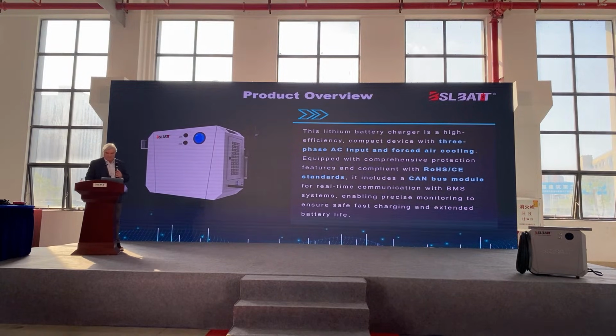So it's a 3-phase AC input, forced air system with variable fans. Depending on the heat load and the environment we're using the charger in, we're able to keep cooling to minimize any stress on the internal components of the charger itself. It utilizes CAN bus module communication, giving us real-time communication with the battery, which enables us to do our proper charging, discharging, cycling, and balancing.